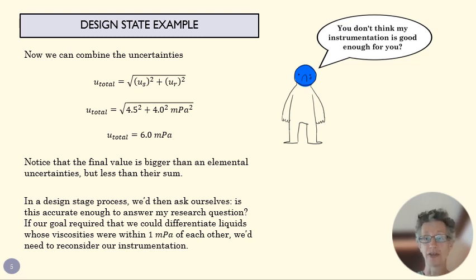So then in our design stage process, if this were a design stage uncertainty process, we'd ask ourselves, is 6 millipascals uncertainty good enough? If for some reason I had a goal of differentiating liquids that might differ in viscosity by only a millipascal or two, I'd look at this and I'd say, oh, that's not going to work. There's going to be too much uncertainty in the values that I produce to actually differentiate these liquids that are very close to each other in terms of viscosity. And in that case I'd have to go back to the drawing board. I'd have to think about getting more expensive instrumentation that's going to give me smaller systematic errors. I'd have to think about how do I keep that temperature really stable throughout the fluid to make sure that my random errors were smaller. And both of those are going to involve spending more money and more time.